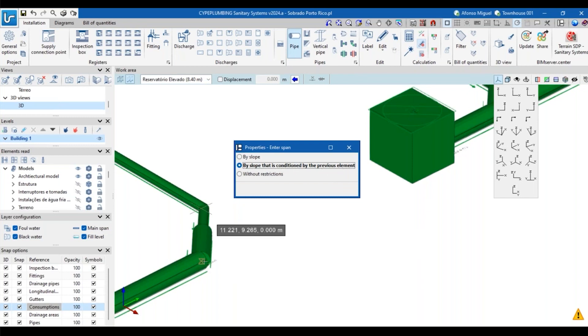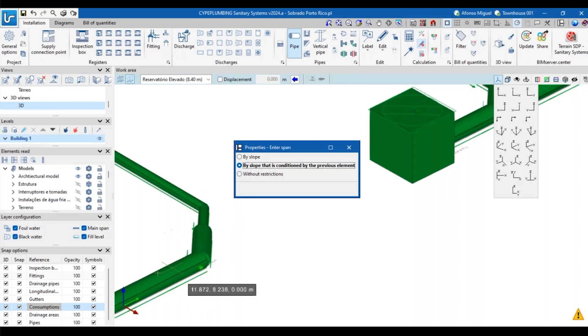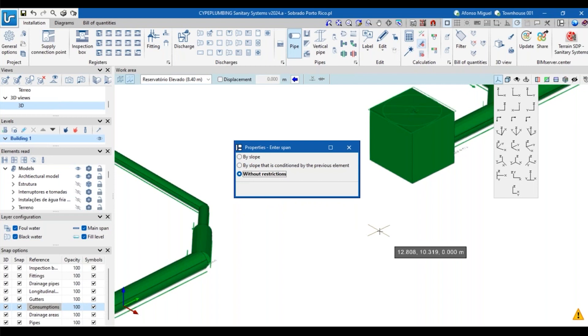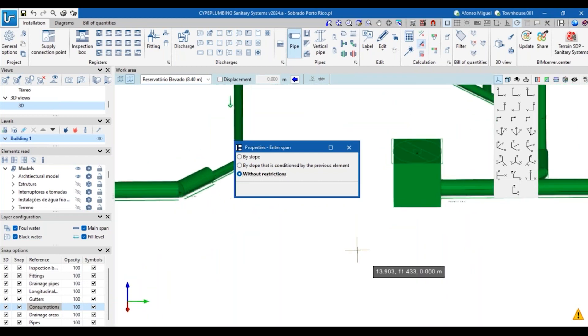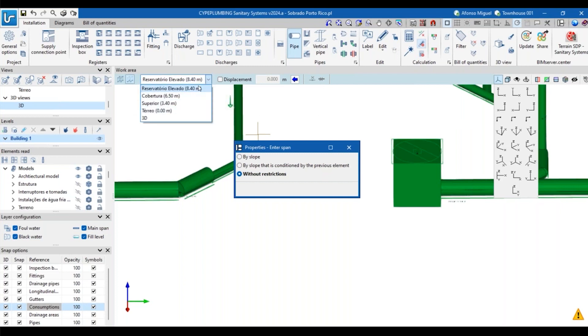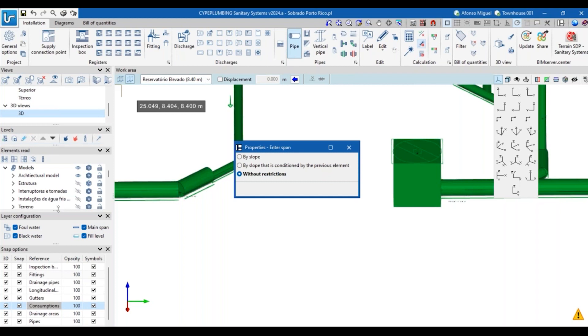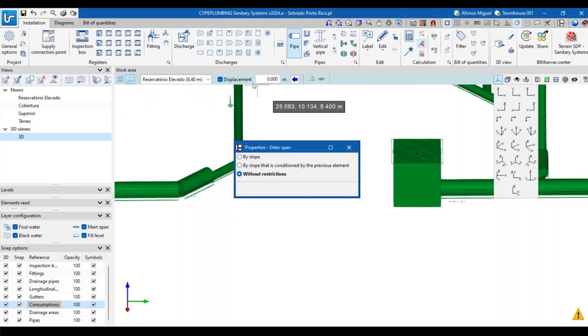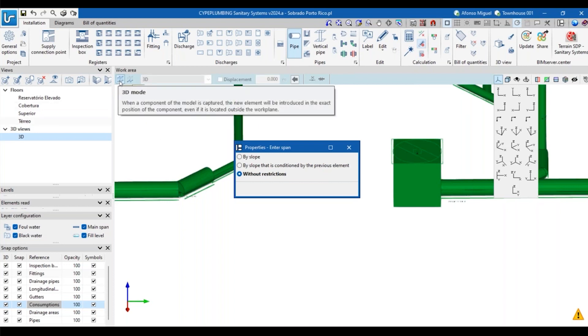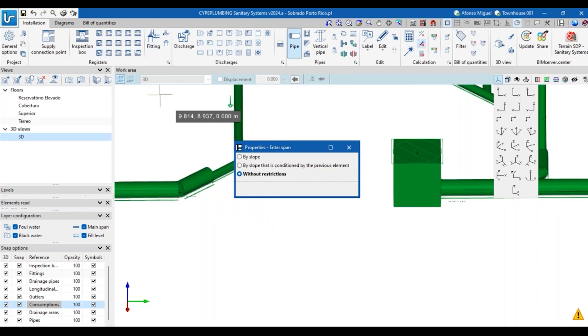It means if I start connecting this new piece of pipe from this one, the slope of this one will be extended, so the pipe would be extended with the same slope to the new section. Or for example without restriction, but then I must know exactly the points that I will be connecting. I can also work with these options here if I'm working with the 2D mode. Basically I will be using one of the views that are created here, the floors, and then applying different displacements to this view, this level. Or I can work totally in 3D by clicking in this option.